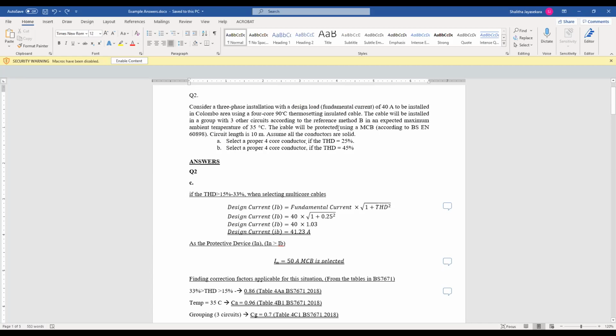Sometimes neutral current can be high, right? Remember, if there are third harmonics, your neutral current will be higher if the third harmonic content is larger than 33%. If that system is fed with a single cable with 4 cores, that means you have to have the neutral sized properly. As I mentioned, in a 4-core cable all the cores are similar. Therefore you should base your design on the neutral current. I think you understand this: if your neutral current is high, you have to design your cable to handle the neutral current, if the THD value is higher than 33%.